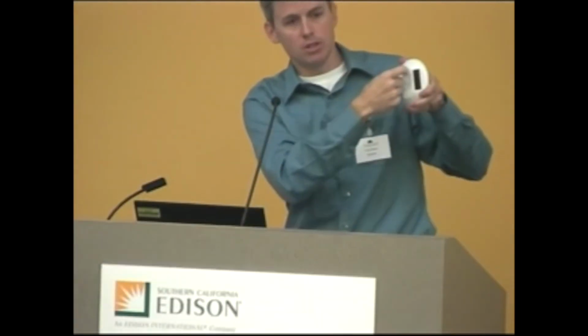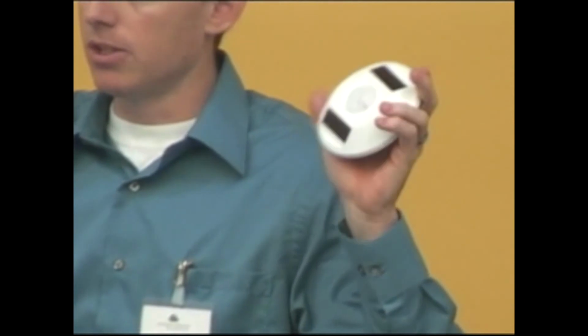There are multiple ways to commission. One way, I can use this device here, it has a little red button. You push the learn button. On this device, you pop this little door off, there's a teach button. You press the learn button, let it go, then press the teach button, and now they know each other. This sends an occupancy sensor profile, so this device knows it just received a signal from an occupancy sensor. Then there are different ways to configure the timeout with a couple of button presses. We also have PC software that can do that during commissioning.